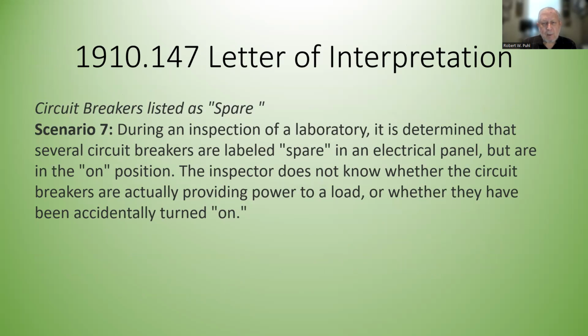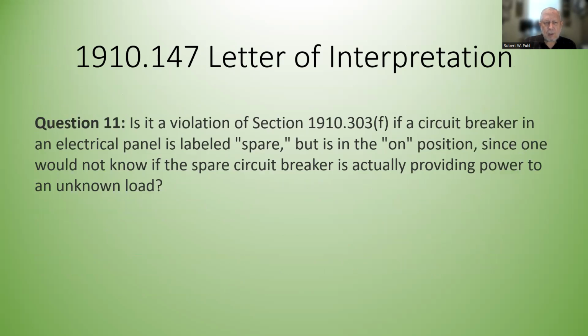During an inspection of a laboratory, it is determined that several circuit breakers are labeled spare in an electrical panel, but are in the on position. The inspector does not know whether the circuit breakers are actually providing power to a load or whether they have been accidentally turned on. Question 11, is it a violation of section 1910.303(f) if a circuit breaker in an electrical panel is labeled spare, but is in the on position, since one would not know if the spare circuit breaker is actually providing power to an unknown load?